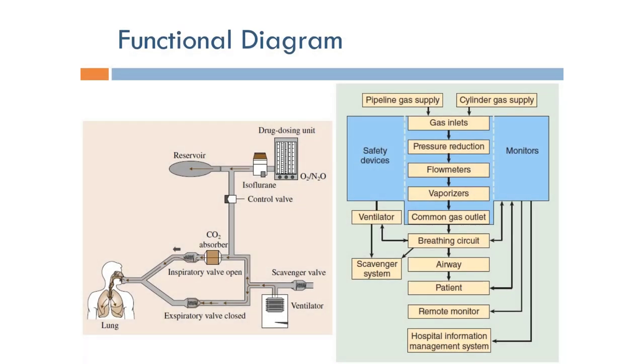The functional diagram of the anesthesia machine starts with the input gas supplies, which can come from cylinders or from the central gas supply from the hospital. These go through gas inlets and must contain oxygen.